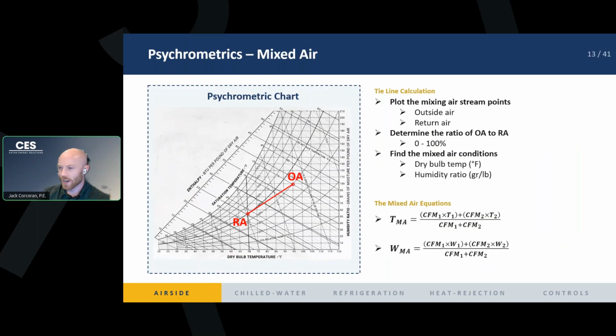bottom. If you just know your CFM total of your outside air and your return air, and then you know your temperatures and your humidity ratios, you can figure out exactly what the mixed air temp is going to be, right? And that's a pretty powerful tool for us engineers to be able to use.